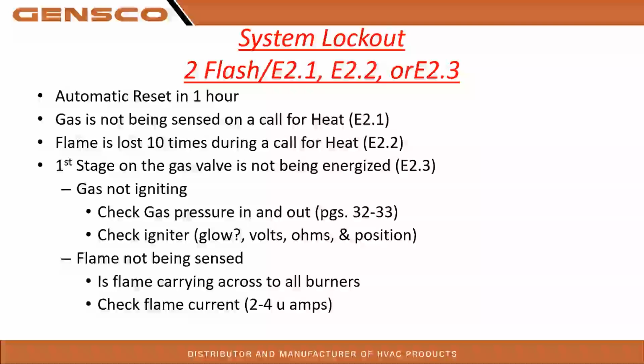We're going to check the igniter. Does it glow? Does it have ohms? Is the positioning good? Is the flame not being sensed? If it is lighting, why isn't the flame being sensed, right? Do we have a dirty burner issue? It's not coming all the way across. It's not hitting a flame sensor. Those kinds of issues we're going to look at.